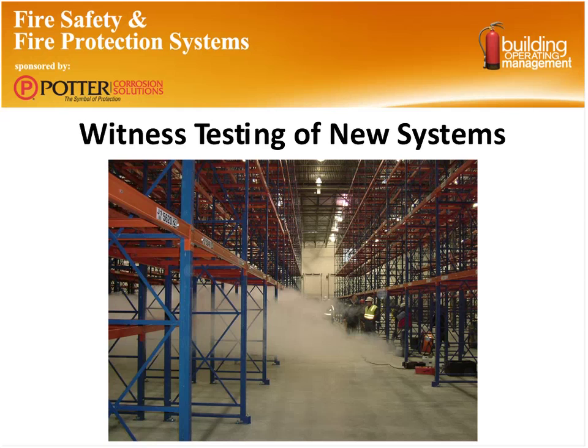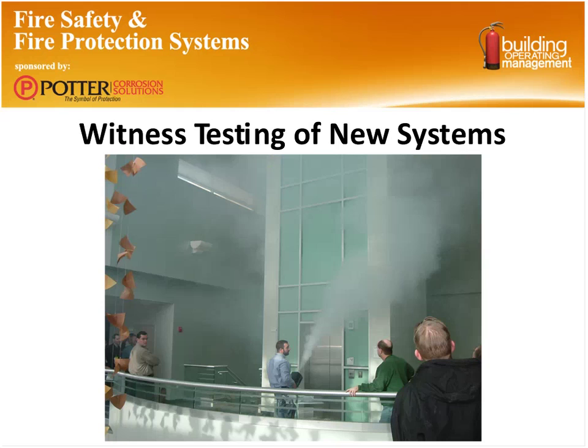But what these pictures are here, this is one of a warehouse testing the actual smoke control system in that case. And this next one is actually at a hospital testing atrium area smoke control systems. Very important piece of the total fire function of the facility, and allows the occupants to safely evacuate and keep that smoke away from them as much as possible during that evacuation through the chosen routes. So with that, that kind of concludes our sections on the fire damper testing and inspection.